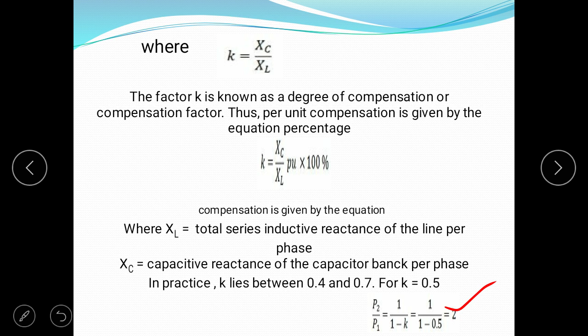Now second is improvement in system stability. How is system stability improved by series compensation? For same power transfer, and for the same value of sending end and receiving end voltage, the phase angle delta in case of a series compensated line is less than for the uncompensated line. The reduced value of delta gives higher stability.